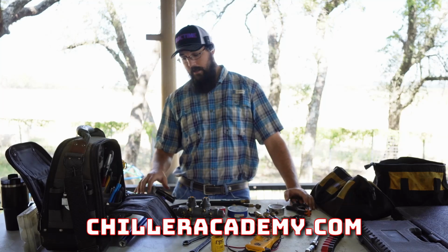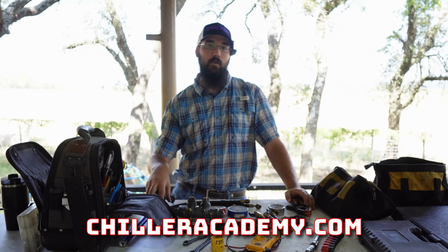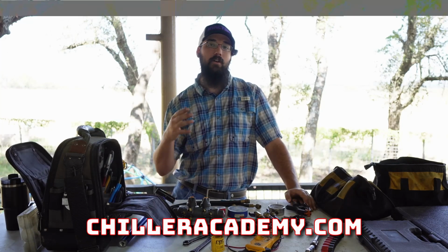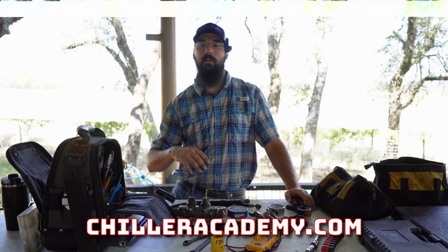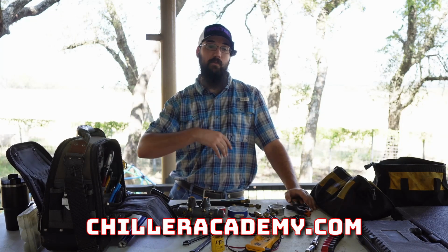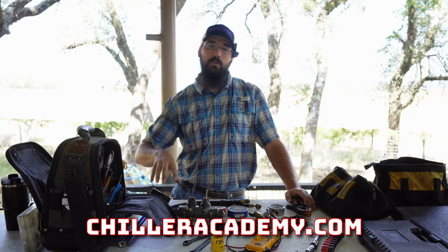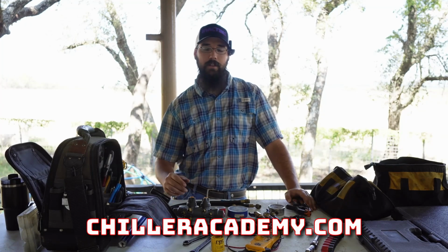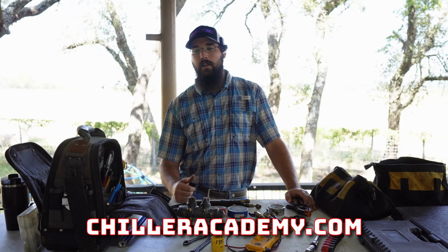So there's a couple of these, but all these are manual, and I am not aware of a battery powered or even corded transfer pump that is designed to operate on chiller oils specifically. They have them for water and stuff, and I just don't know how much I trust that for getting into what we do, right? We have to be careful with these things. So an oil transfer pump is going to be a core part of your kit. We have to transfer and move oil, mostly add oil a lot. So being able to do that is going to be essential.